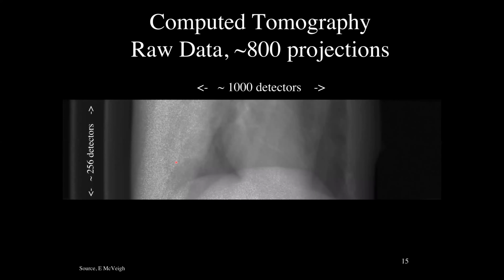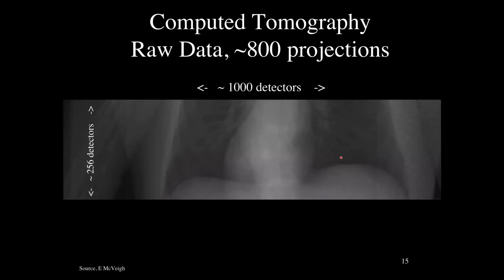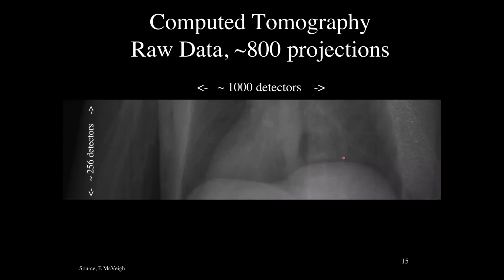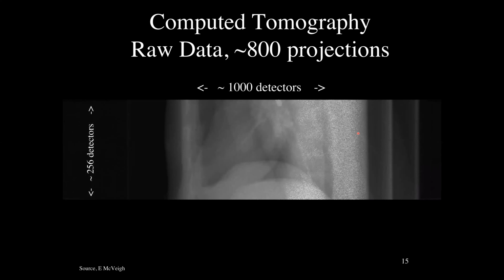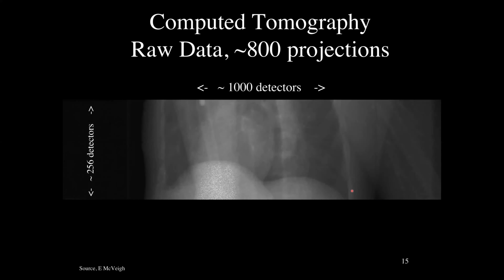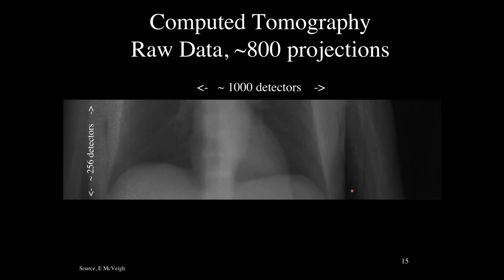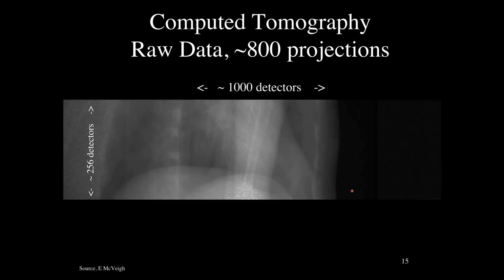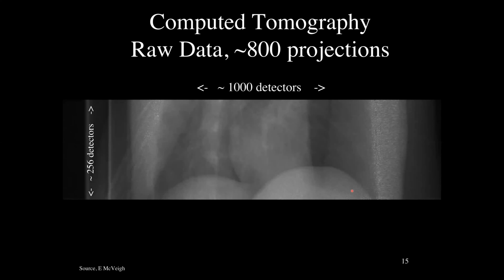And you can see also that the signal gets a little nasty when we have a very long path that the X-rays have to come through, because many of the X-rays get absorbed and you're left with just a few, like tens of X-rays on your detector. And so you get very high noise at that time. However, if that noise is outside the field of view you're interested in, you can usually compensate, not let it wreck your picture, by filtering it in some spatial way.